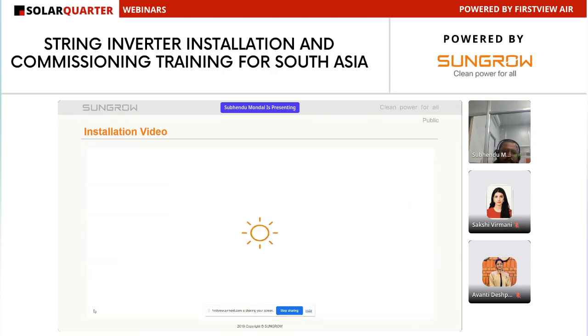So firstly, we have to unpack the inverter. After unpacking, we have to check that one inverter is received inside the box. We have found MC4 connectors, an AC gland, and some screws to mount the mounting bracket to install the inverter. Then we have to ensure that we are working with proper PPE and proper tools before installation. Then we have to install the inverter vertically, as you have seen in the video, or with up to 10-degree tilting. Next is clearance: ground, top, side, and front clearance should be as per the user manual, as I already told.